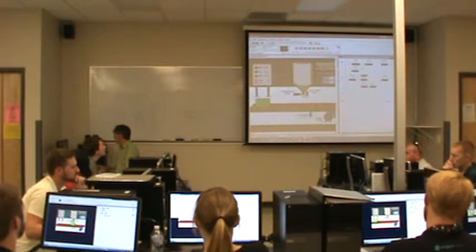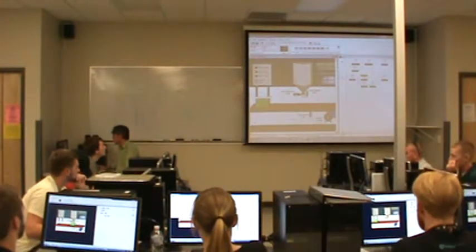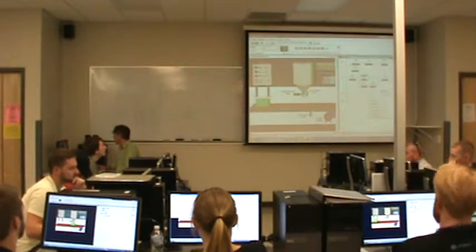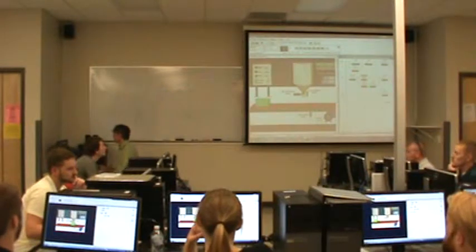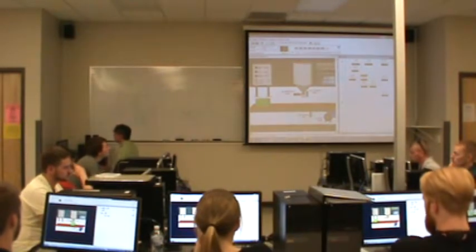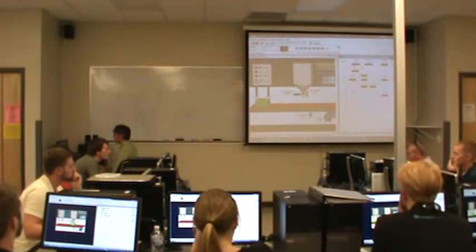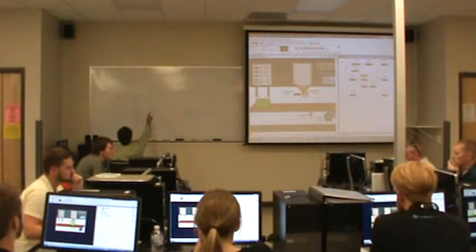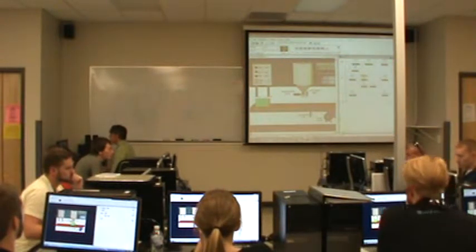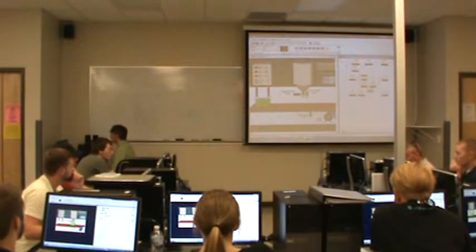All right, so what am I doing? Not the motor output, the solenoid valve output. Edit symbol, call this valve. The conditions for valve being true, well, our default condition is that the run lamp has to be on. We don't want any of this code to execute without the run lamp being on. But our decision was that we want prox true, level not true for the valve to come on. So we want prox true, in other words, a box in place that is not full.